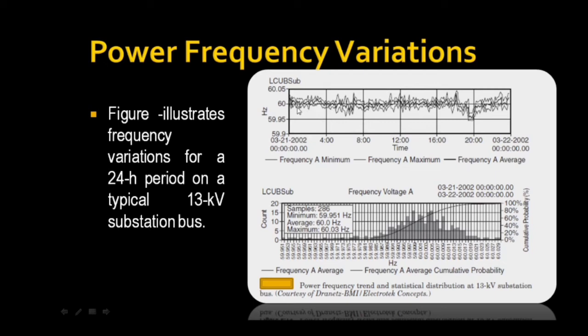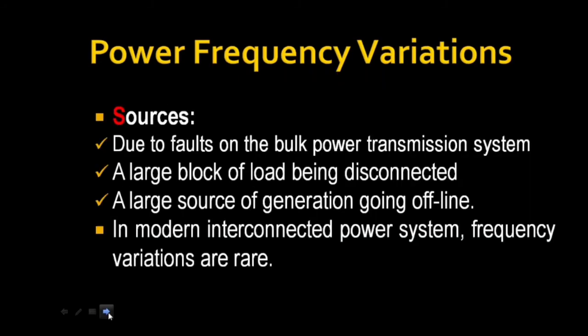Observe this diagram clearly — there is a power frequency variation, that is the deviation from the normal frequency value. From the sources point of view, power frequency variations can be caused by faults on the bulk power transmission system, a large block of load being disconnected, or a large source of generation going offline.